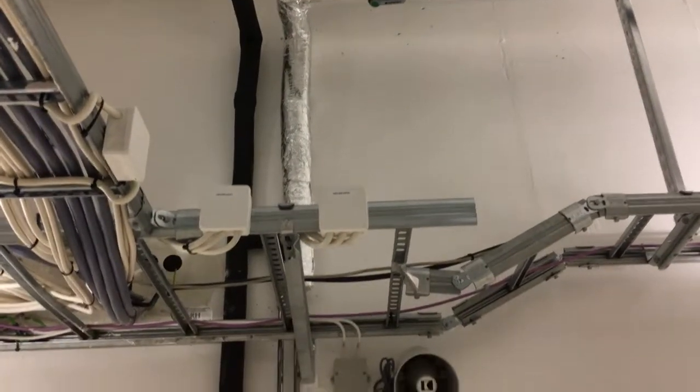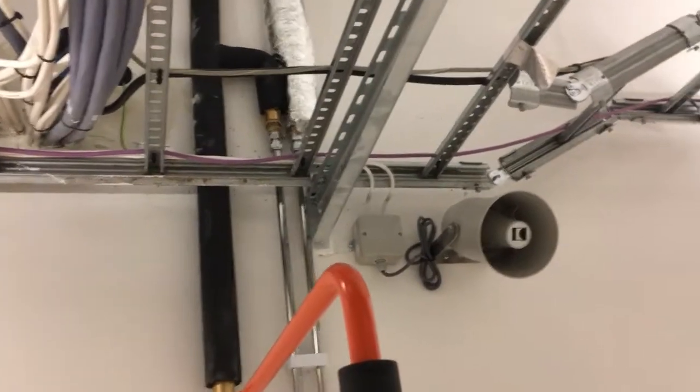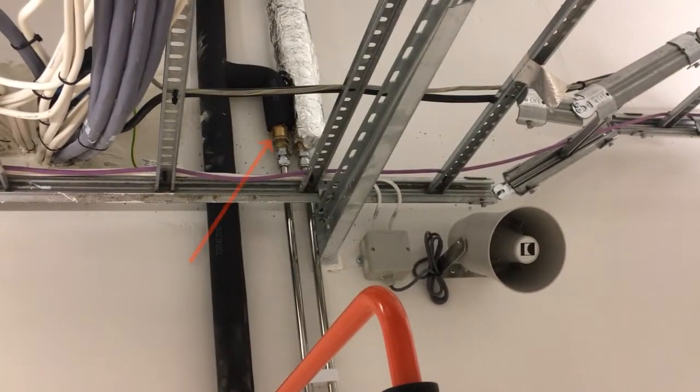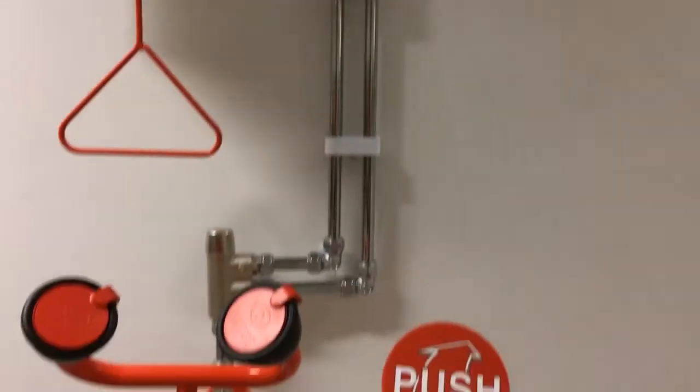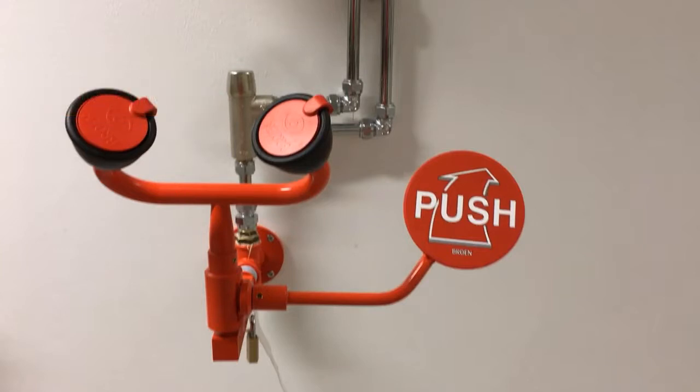And these two things are coming together. First you see the cold coming down, copper pipe of the main domestic water supply, coming down to this nice chromed fitting going towards the appliance at the end of it. And you see the hot water coming in here, which are going to be mixed down here in a mixing valve. And here we have the eye wash station. So if there'd be an accident in this laboratory and somebody needs to flush out their eyes, of course we don't want to have burning hot water or freezing cold water, and so we get a mix of these two. You put your eyes to this, push on the handle, and clean out your eyes from any spills that have gotten in there.